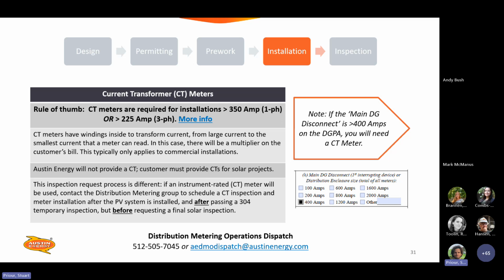They have windings inside to transform the current from large to small so that our meters can handle it without being damaged. In this case, there'll be a multiplier on the customer's bill, and this typically only applies to commercial installations. Austin Energy does not provide the CTs, so you'll need to go to our website and look at the approved meter socket list, and there'll be a list there of the specs for approved meters. Also, I included that link there too, so that's the letter from our engineering team from like 2017, I think, that calls out what we approve in CTs.